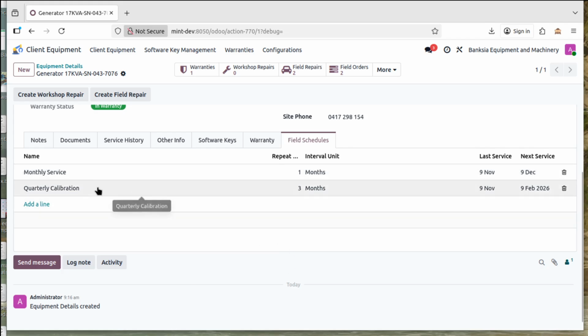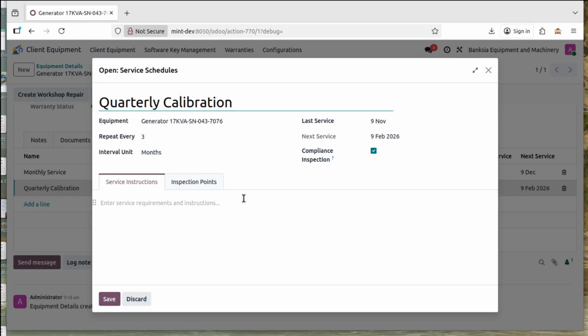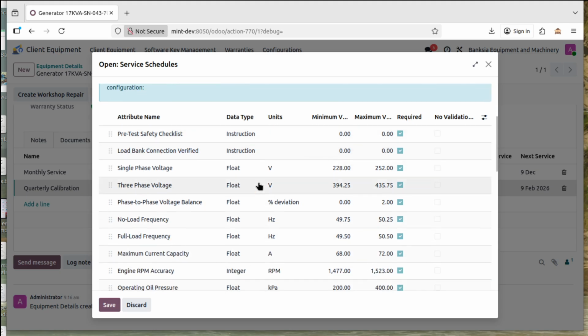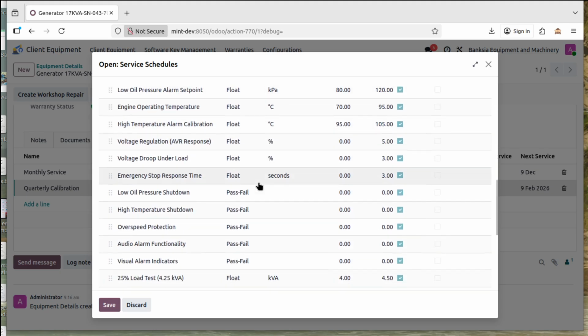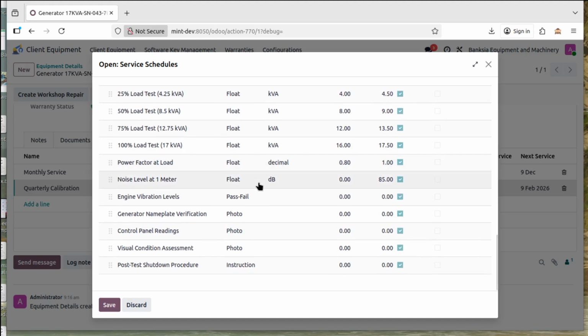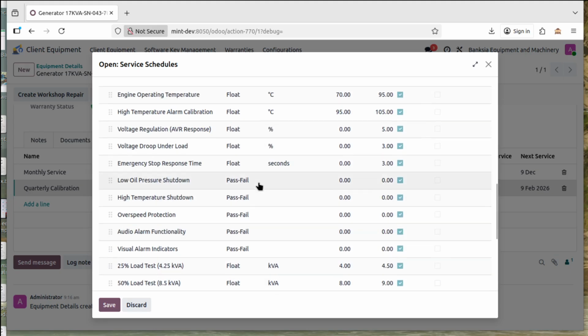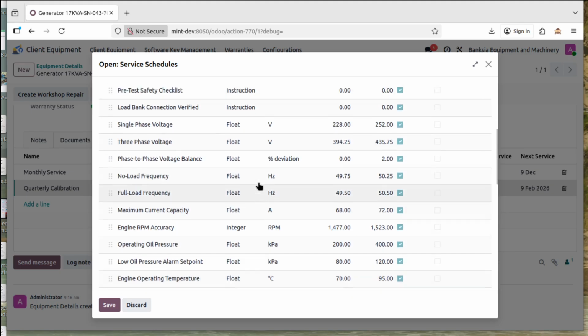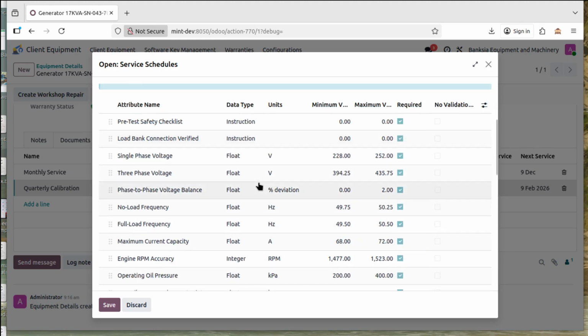We've also got this one, which is a quarterly calibration check. So once a quarter, we're required either by some sort of contract, agreement, or compliance to go out and do a calibration check on this particular piece of equipment every 3 months. Because this is ticked as a calibration inspection, I get my calibration points in here, my inspection points, and as you can see for this particular one there are quite a few to check off - they're really checking the entire integrity of the system throughout this quite comprehensive calibration check.